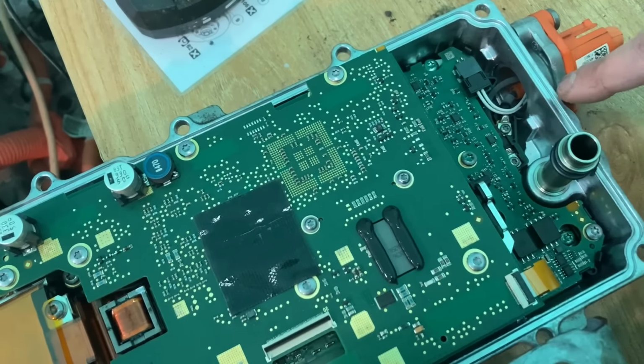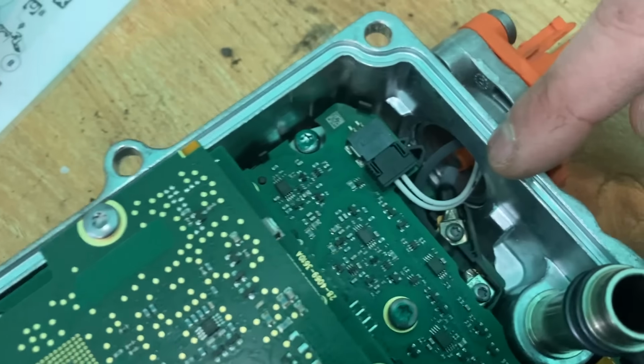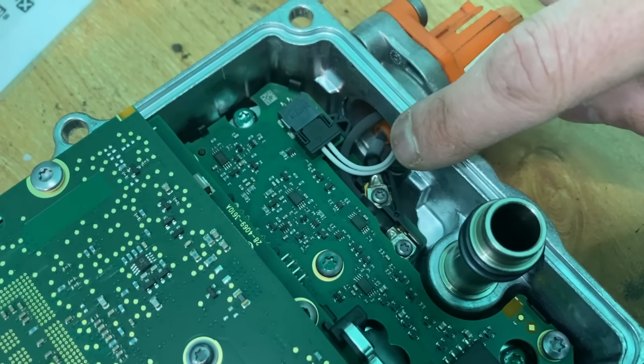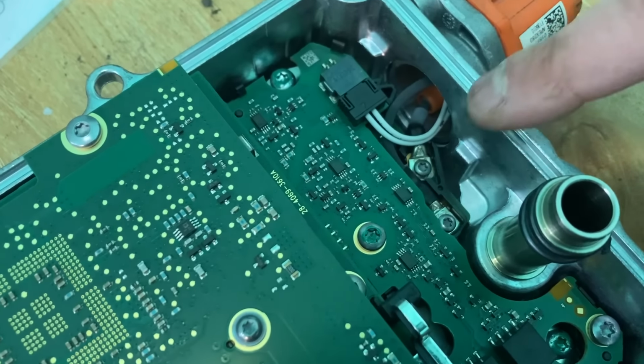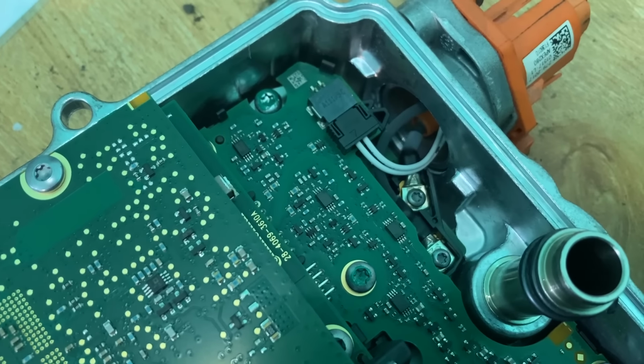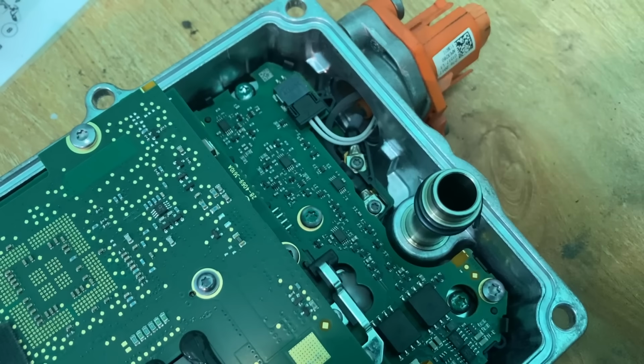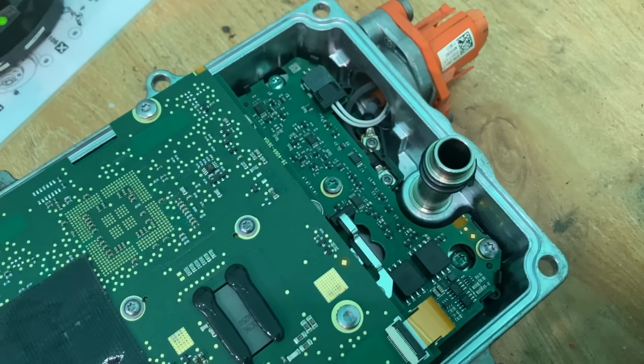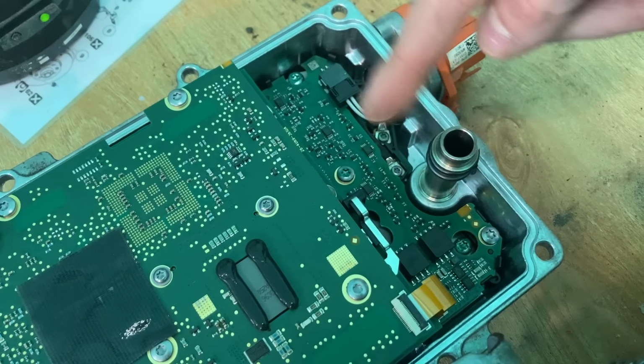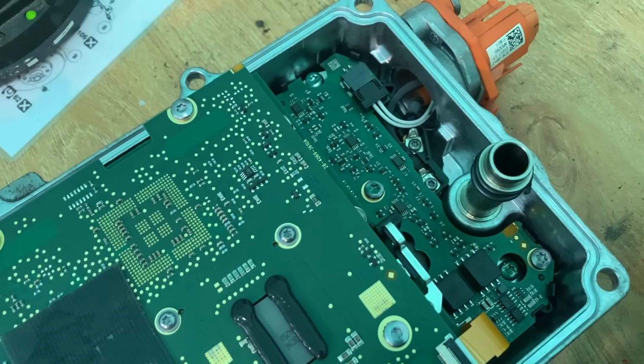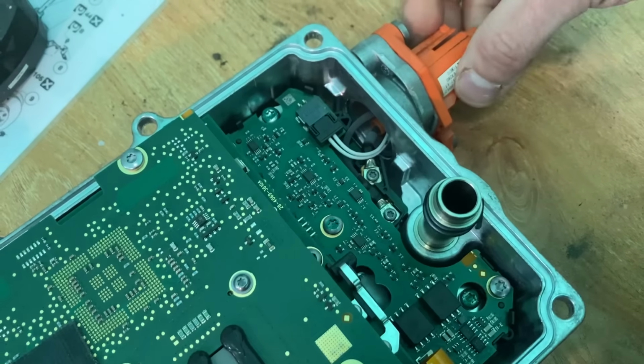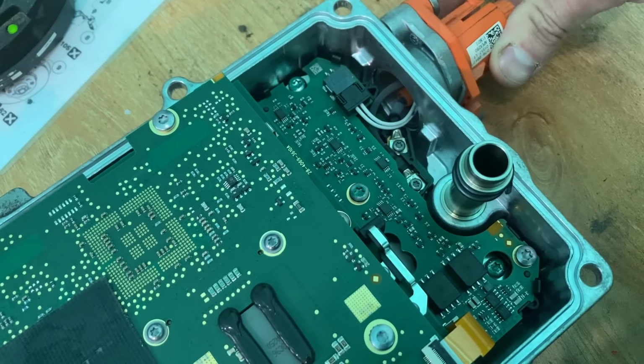First interesting thing to note: down here there's possible evidence of a bit of overheating, because that looks a little white down there, so we need to investigate that. Obviously I can carry out the insulation test in here and work out which module, but I kind of suspect this excitation module. That's the connector that goes to the brushes onto the rotor.